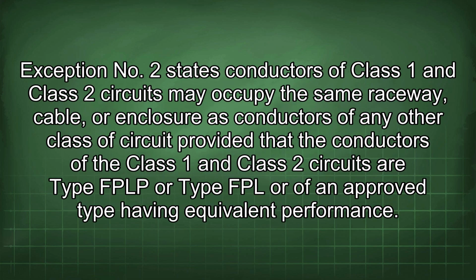Exception No. 2 states conductors of Class 1 and Class 2 circuits may occupy the same raceway, cable, or enclosure as conductors of any other class of circuit, provided that the conductors of the Class 1 and Class 2 circuits are Type FPLP or type FPL or of an approved type having equivalent performance.